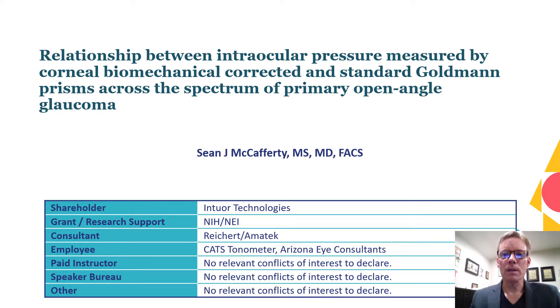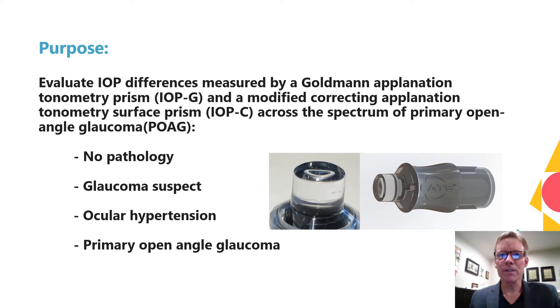I will be discussing the relationship between intraocular pressure measured by a corneal biomechanical correcting prism and a standard Goldmann prism across the spectrum of primary open-angle glaucoma. The purpose of the study is to evaluate differences between IOP measured by a Goldmann applanation tonometry prism and a modified correcting applanation tonometry surface prism. The modified prism incorporates a concave convex surface designed to significantly decrease the Goldmann tonometer's sensitivity to corneal biomechanics without overall population IOP bias.